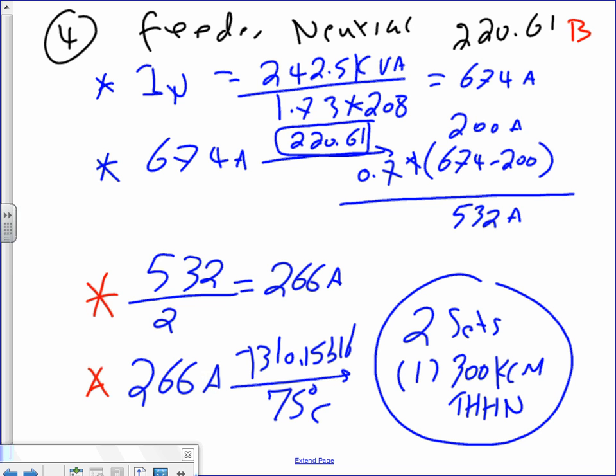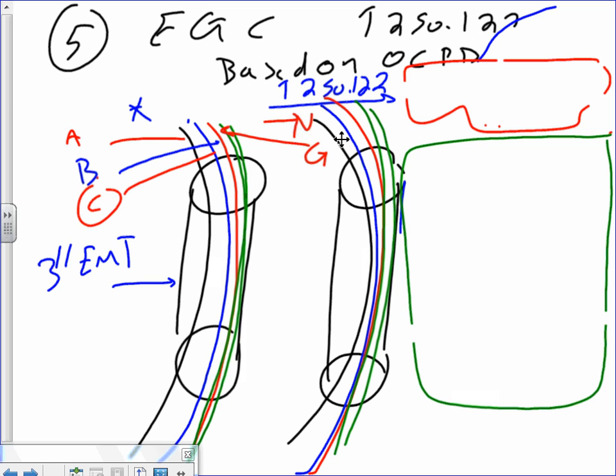One last thing, and then I'll give you a break. The equipment ground conductor. Take the 700 kcm guy. For the equipment ground conductor, take the fuse or circuit breaker size to the same table, 250.122. That will get you one conductor, number 1 AWG.